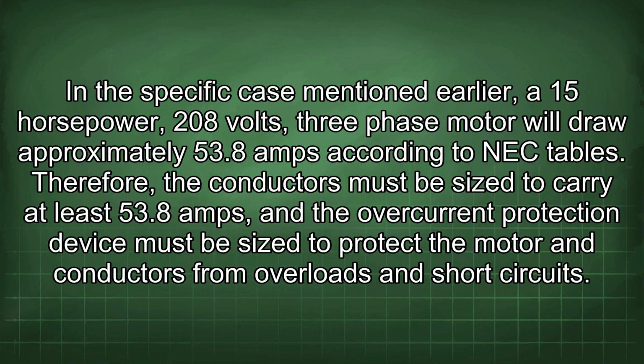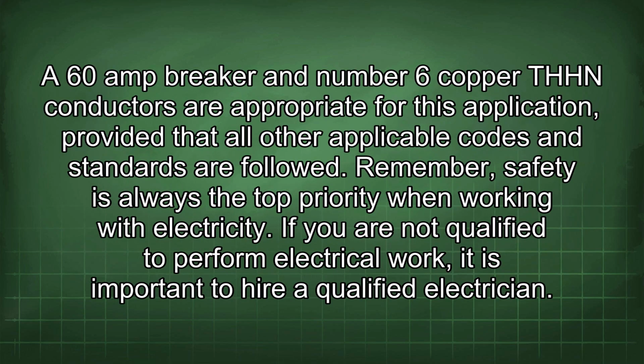In the specific case mentioned earlier, a 15 horsepower 208 volts 3-phase motor will draw approximately 53.8 amps according to NEC tables. Therefore, the conductors must be sized to carry at least 53.8 amps, and the overcurrent protection device must be sized to protect the motor and conductors from overloads and short circuits. A 60 amp breaker and number 6 copper THHN conductors are appropriate for this application, provided that all other applicable codes and standards are followed.